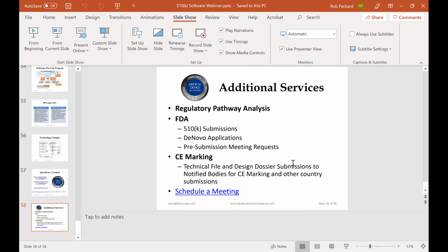And it's basically saying we've made the following design revisions over time, and each one was documented under a letter to file, and we're submitting this catch-up 510K to get the FDA's documentation current with what we currently have on the market. That doesn't mean that you have to get the FDA's approval prior to release, because you've already released it. You're just trying to get your documentation of your 510K current with what's in the field.